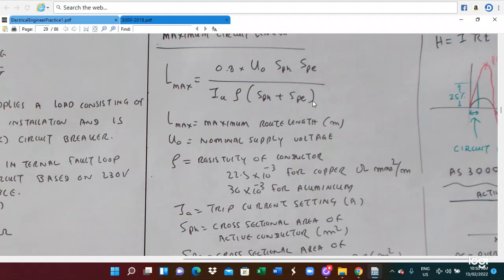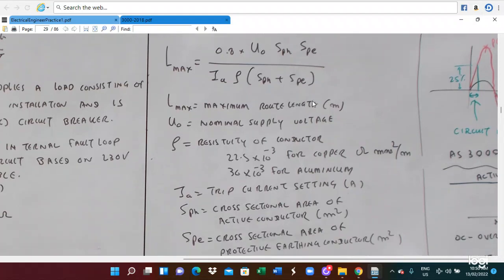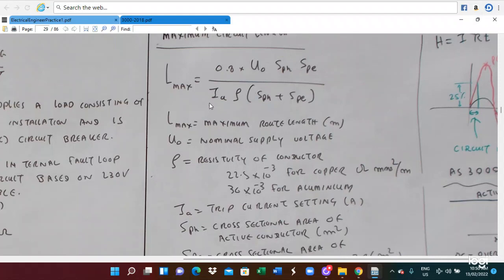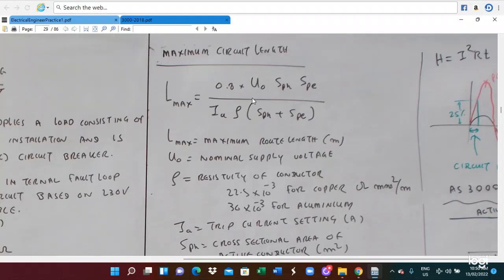So those things you have to find out. If you know the supply voltage U0, SPA the cross-sectional area of the active conductor, SPE the cross-sectional area of the protective conductor, IA the trip current setting, and rho the resistivity of the conductor, then you substitute those factors in the formula, and you can calculate the maximum route length. So this means how long you should draw the cable. This is the maximum circuit length.